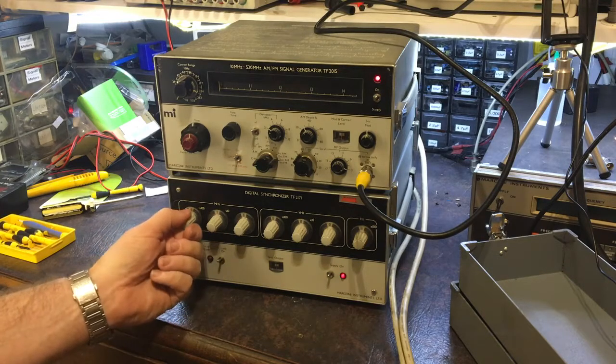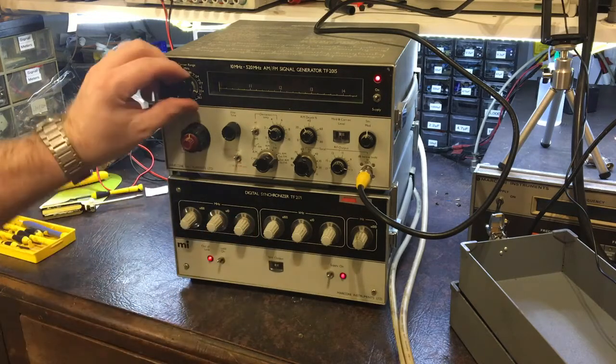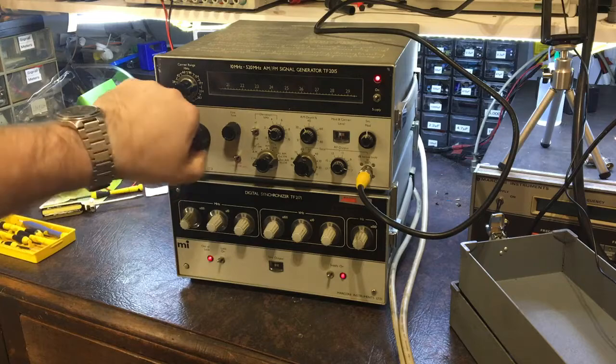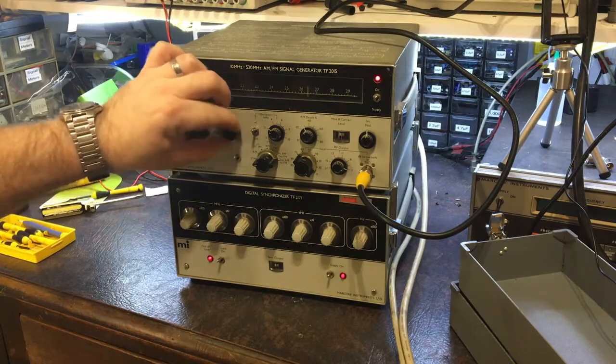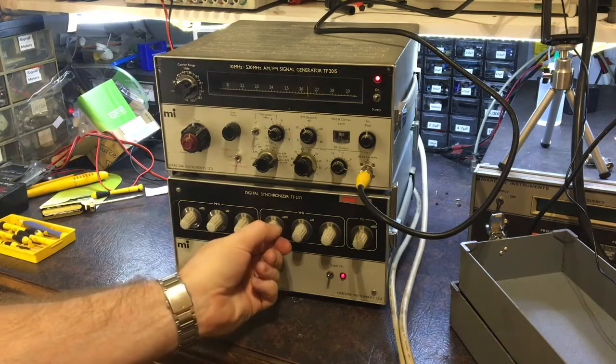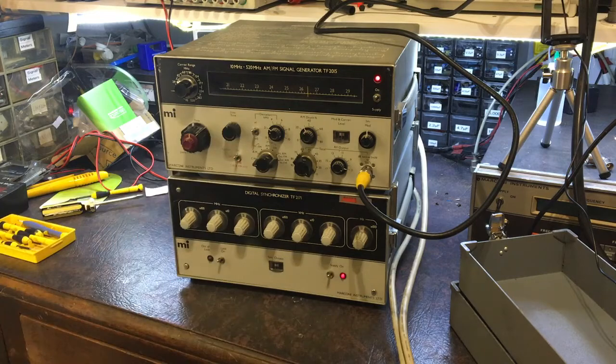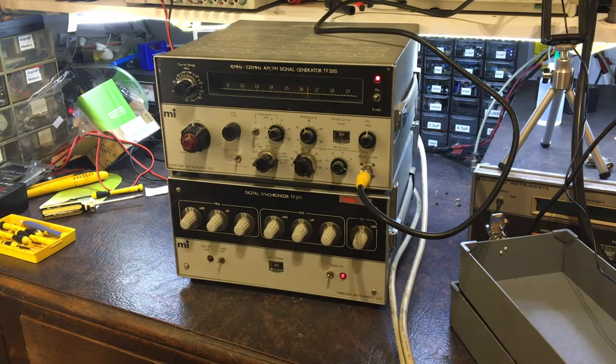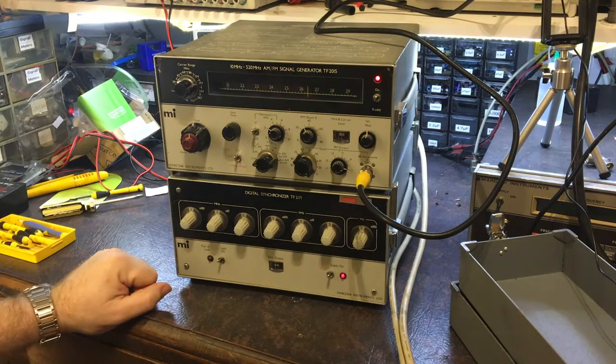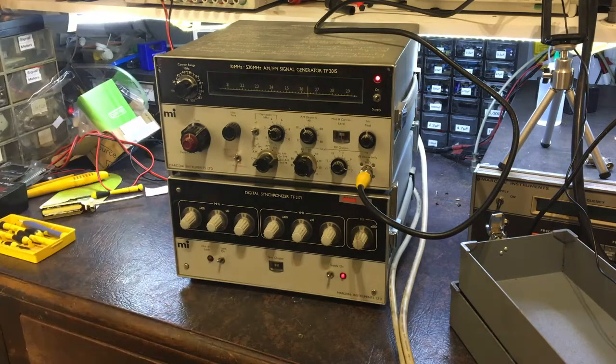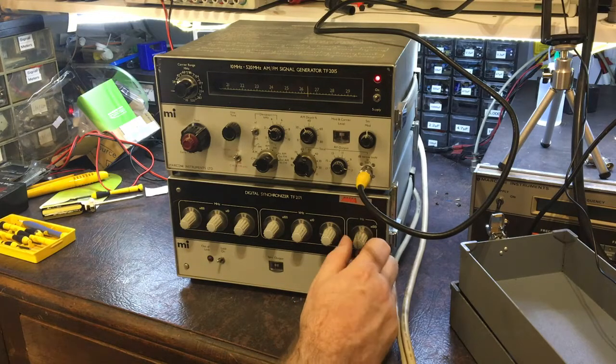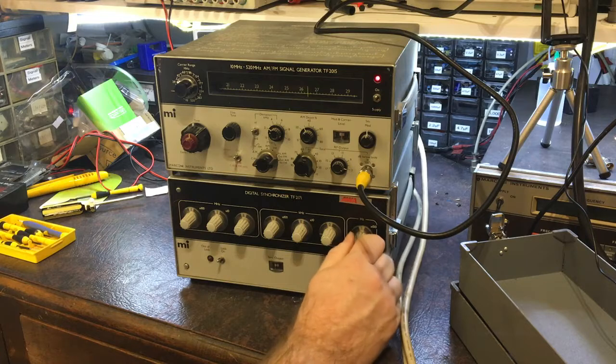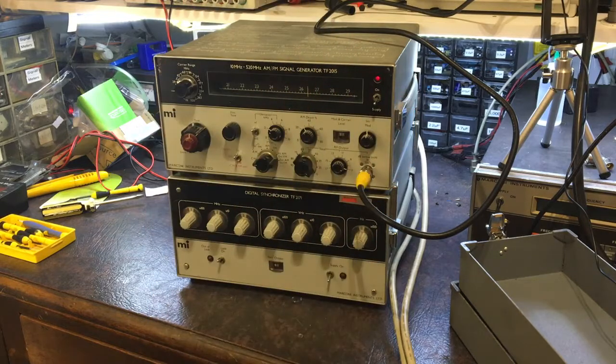It's just a bit fiddling around getting it set, but it's not quite as straightforward as the other Marconi. You just hit a couple of buttons and you're done. But it works fine. That's bang on 26.5 MHz. So we can do 100 Hz steps, that's what steps it can do. Yeah, all good, still works.